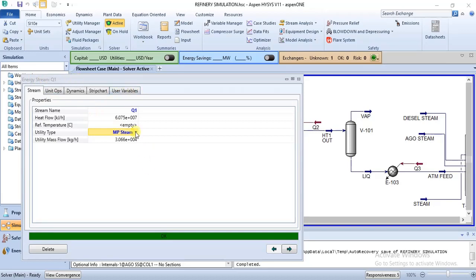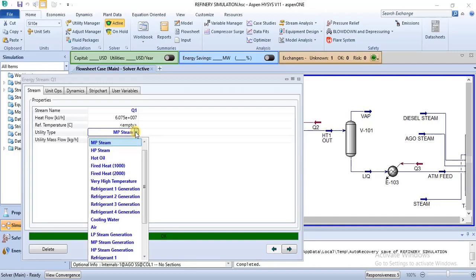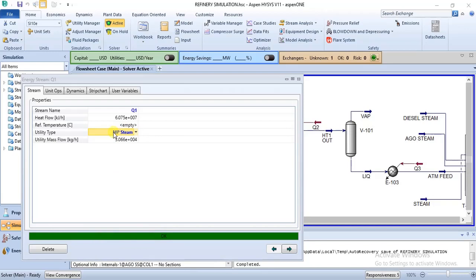MP steam is suitable here because the temperature difference across this particular unit is not very high. If the temperature difference were quite higher, steam may not be suitable — we may have to use either hot oil or fired heat, which are required for very high temperature changes. So now I've specified MP steam and it has calculated the mass flow. The mass flow is calculated based on the utility you choose.